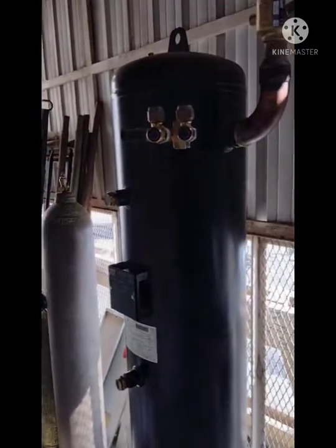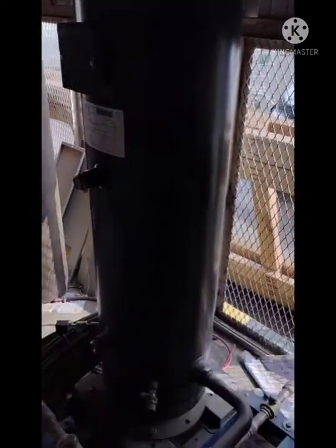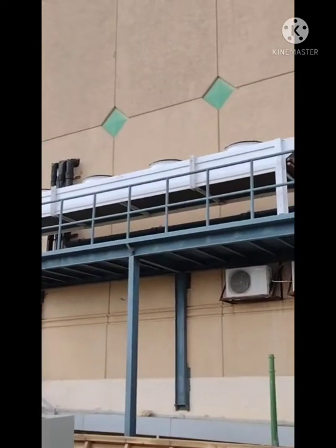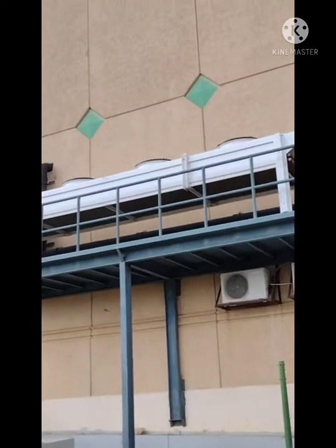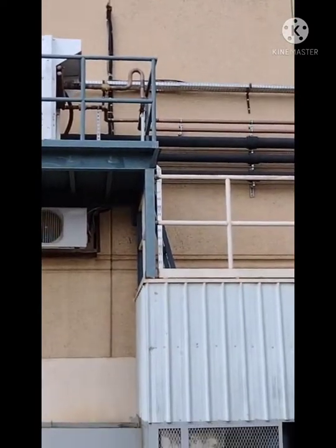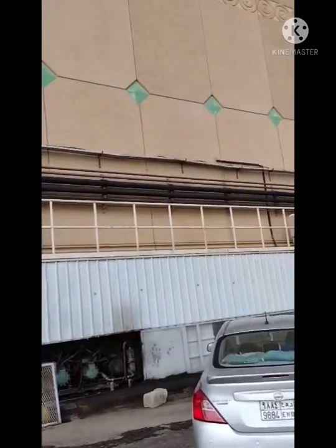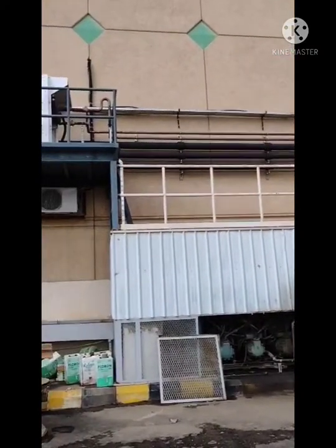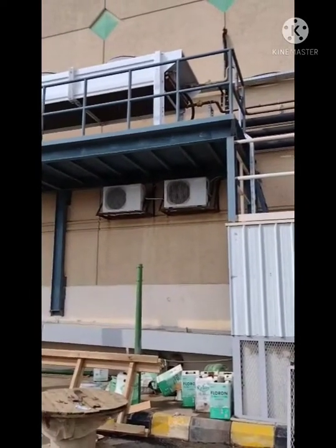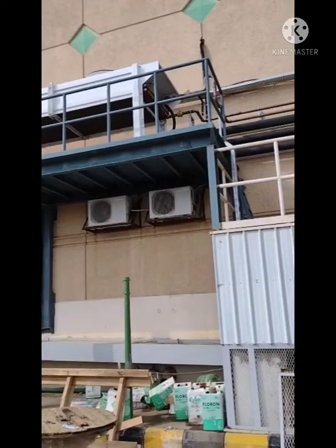This is a liquid tank. This is the condenser, which has four condenser fan motors. The two pipes coming in are for discharge and liquid line — one is in and one is out.